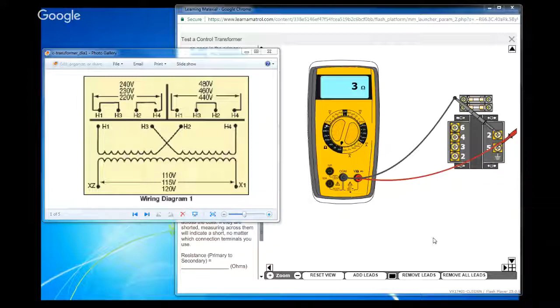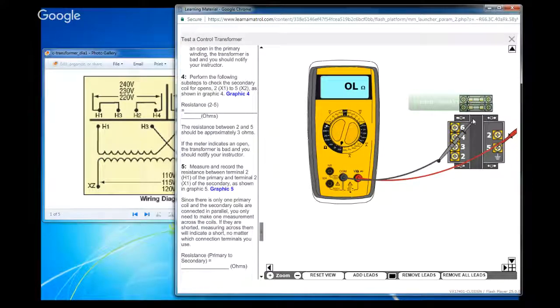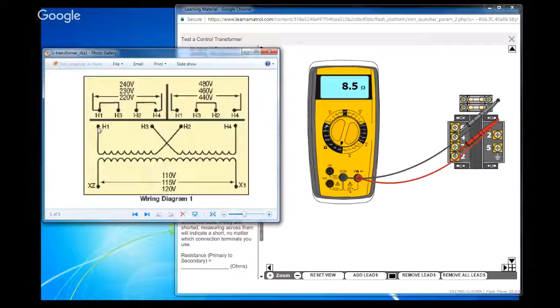So here we have our virtual meter, and it's set for 200 ohms, and I'm checking the secondary winding of this control transformer, and I see that it's stable at 3 ohms. So let me check. We don't know which one's on here, but we do know it's H1, H3, H2, that if we start from the bottom, 2 and 4 should be one set of coils. And so let's check here and check here. And so now I'm checking from H1 to H2, and I'm reading 8.5 ohms.